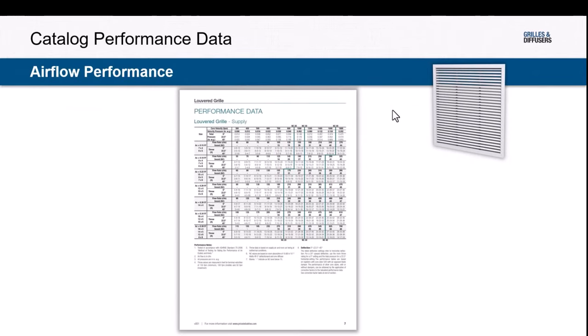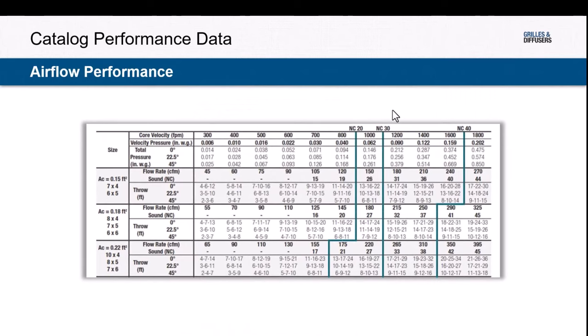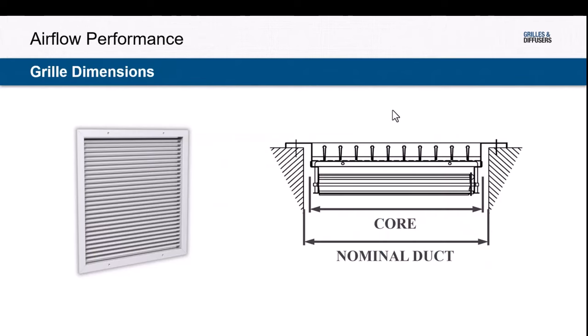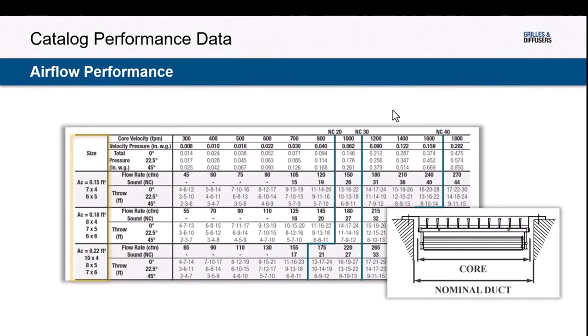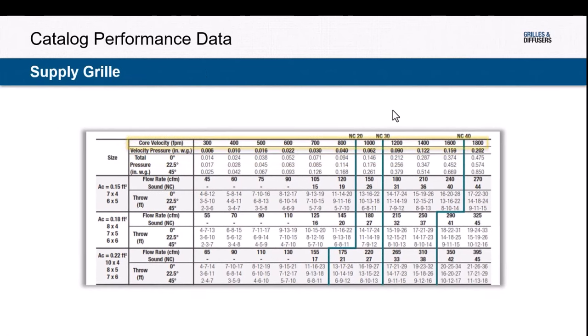Looking at a catalog page for a single deflection louvered face grill, there are a range of sizes along the left-hand side. When it comes to grill size, we talk about two different dimensions: a nominal duct dimension and a core dimension. The nominal duct dimension is literally the opening of the hole you're trying to fill. It is the core area that drives the performance of the grill. In this example, an 8x4, 7x5, or 6x6 grill all have a core area of approximately 0.18 square feet, and we can look at performance across a wide range of air velocities.